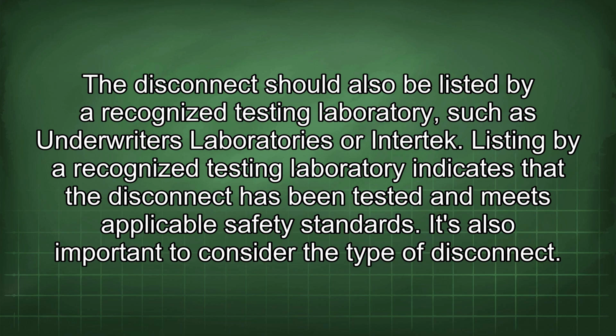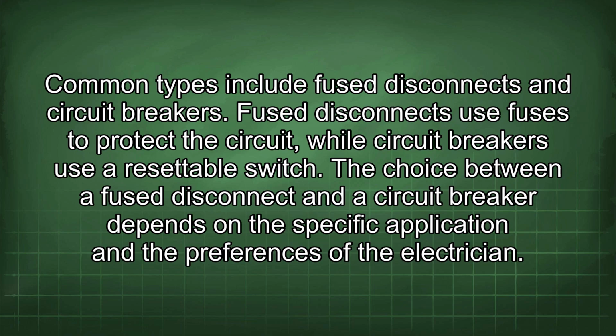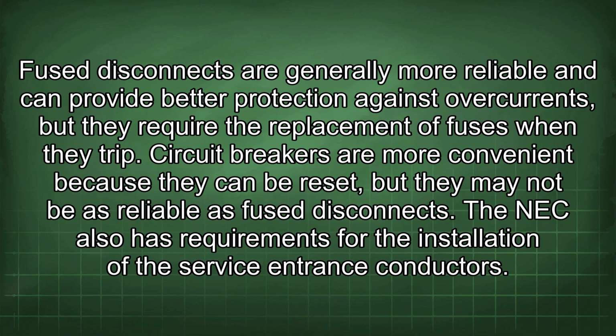It's also important to consider the type of disconnect. Common types include fused disconnects and circuit breakers. Fused disconnects use fuses to protect the circuit, while circuit breakers use a resettable switch. The choice between a fused disconnect and a circuit breaker depends on the specific application and the preferences of the electrician. Fused disconnects are generally more reliable and can provide better protection against overcurrent, but they require the replacement of fuses when they trip.